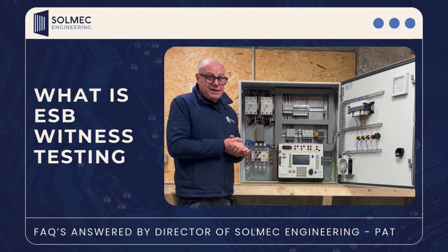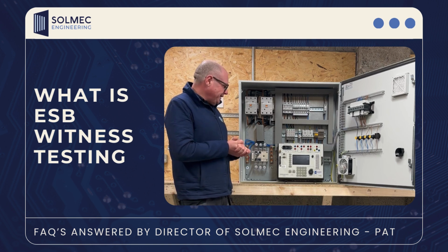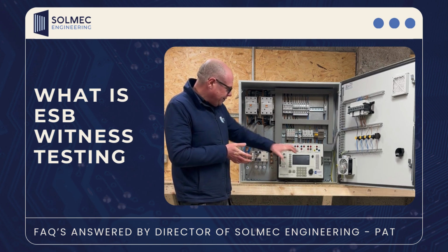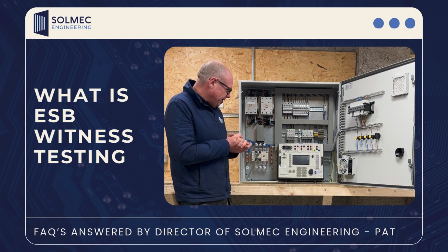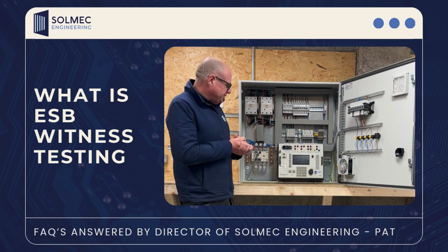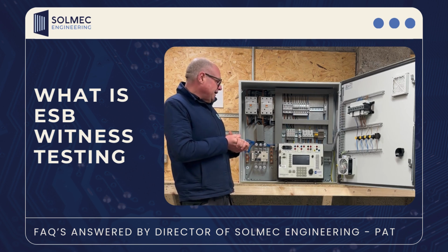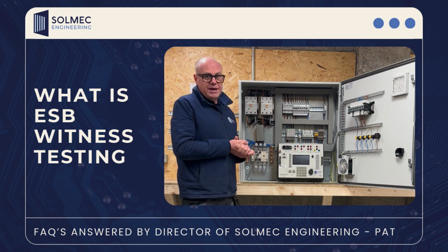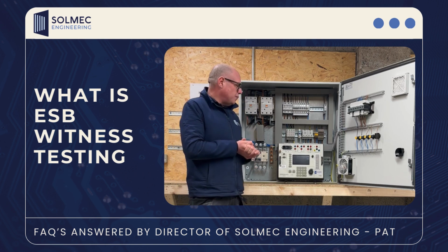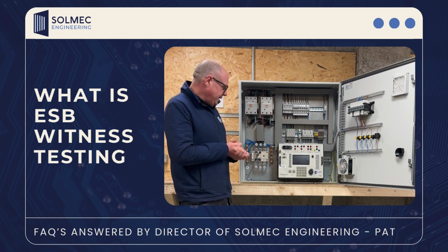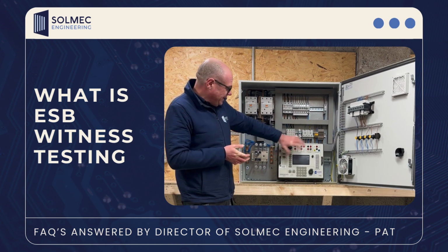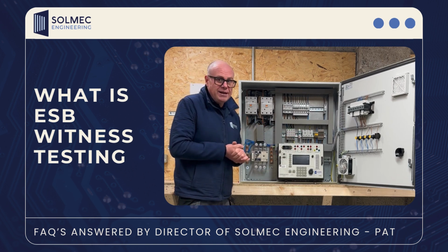How do we simulate these fault conditions? We simulate them with testers. This is a testing kit that I went over to England and got a long time ago now, but it's one of the best testing kits I've ever used. It can inject voltage, it can inject frequency, and it can simulate a loss of mains through rate of change of frequency, or ROCOF as we call it in the trade. I also have a very similar tester that injects current as well.